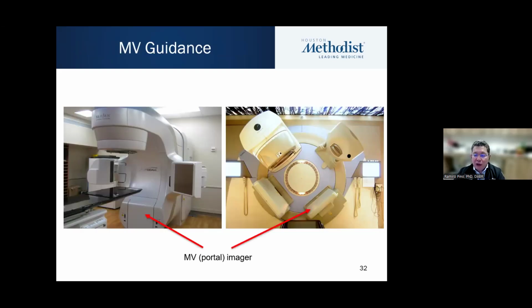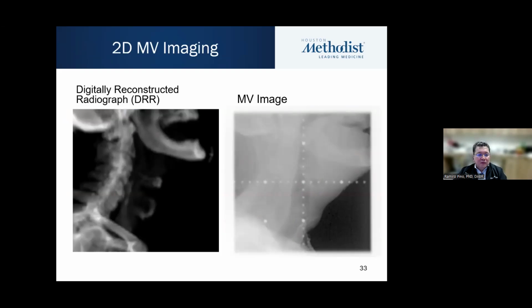So now we're going to image guidance. I'm going to mention here that you could use a portal imager to do image guidance. And in this case, we're using the beam to actually image the patient. And that's what we call the MV or portal images. I'm showing here two commonly used machines, a Varian and an Elekta machine. And typically, we do a comparison between the image acquired and the digitally reconstructed radiograph from the CT scan that we acquired for simulation. And based on that comparison, we can determine shifts, and we can apply them.